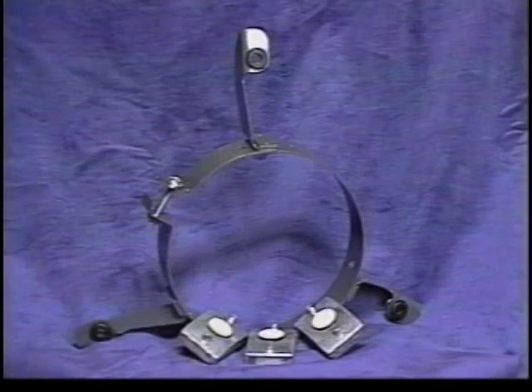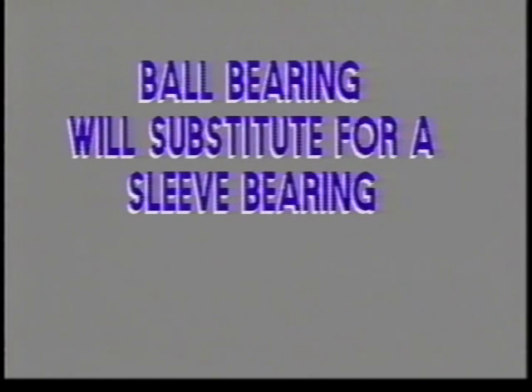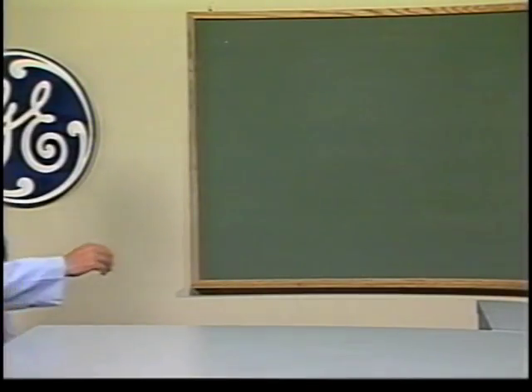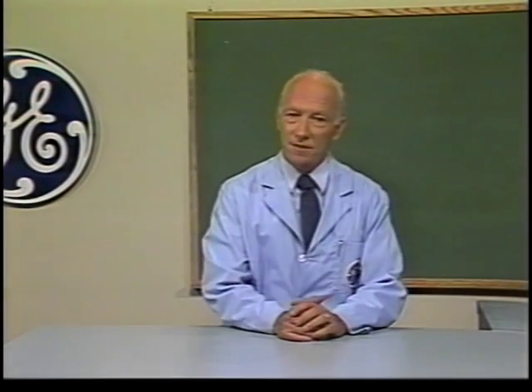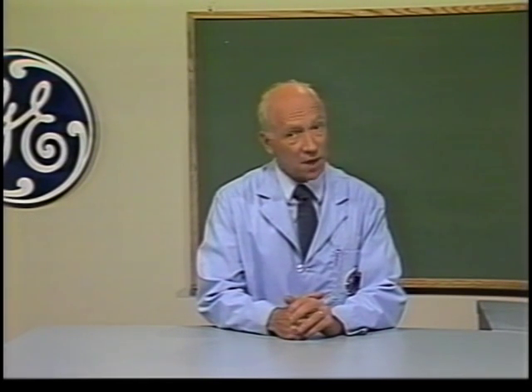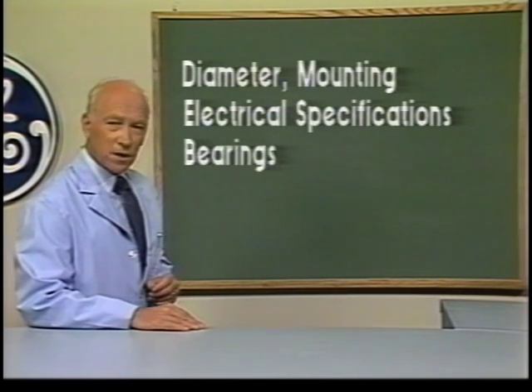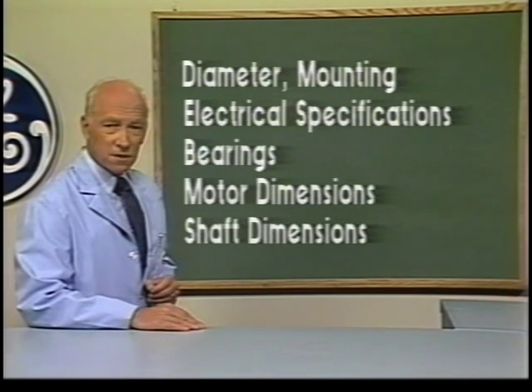The next step is to go down a checklist of mechanical and electrical specs to find a suitable match. Use the motor description section of your guide and start with the diameter, then check for horsepower, voltage, frequency, rotation, amperage, and RPM. Also check the number of speeds, match the enclosure and the mounting — remember there are many mounting adapters available. Check the bearing type: a ball bearing can be substituted for a sleeve bearing, but not the opposite, as sleeve bearings won't hold up under the loads found in ball bearing applications. Also look at the motor's dimensions.